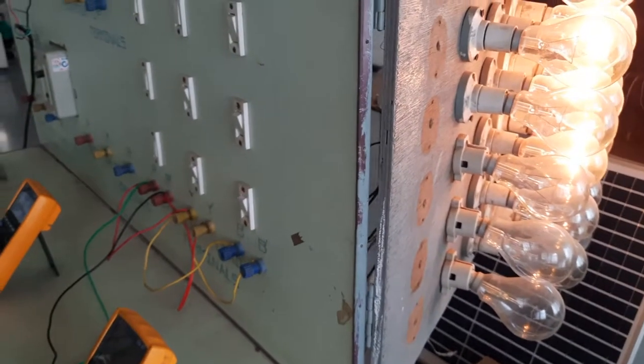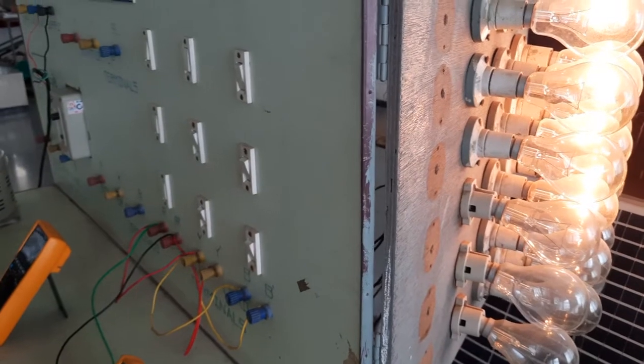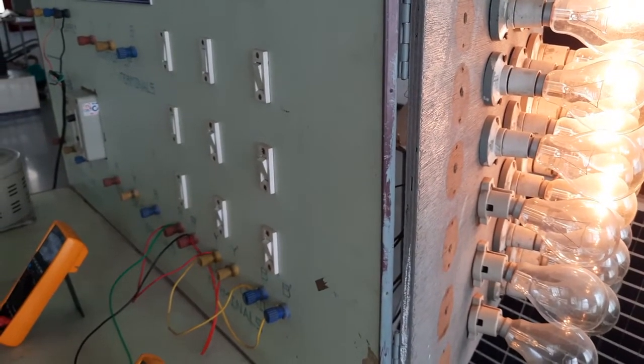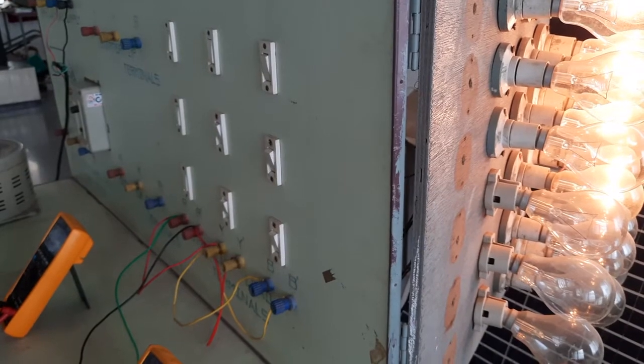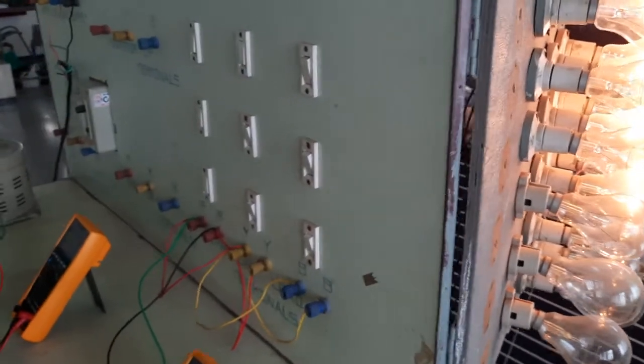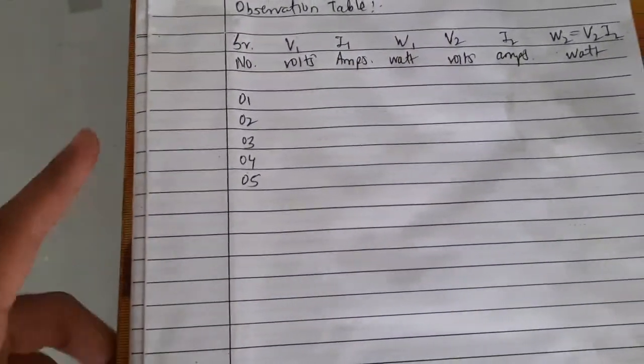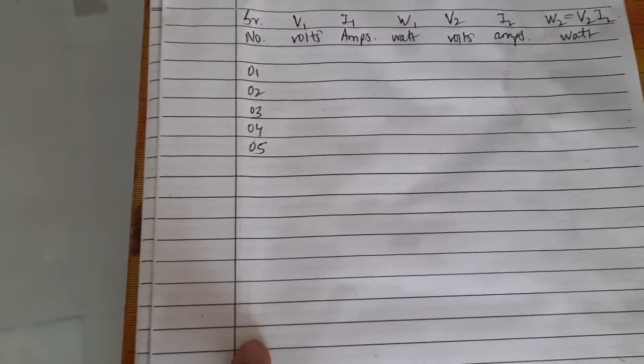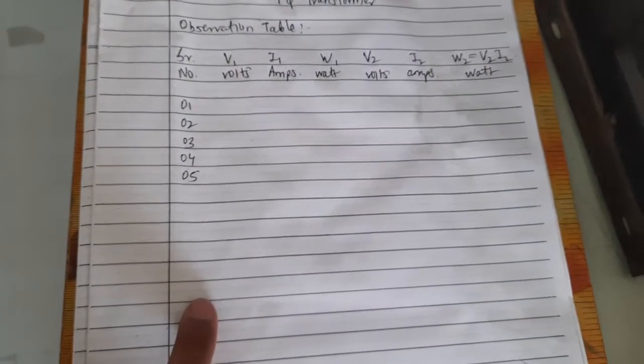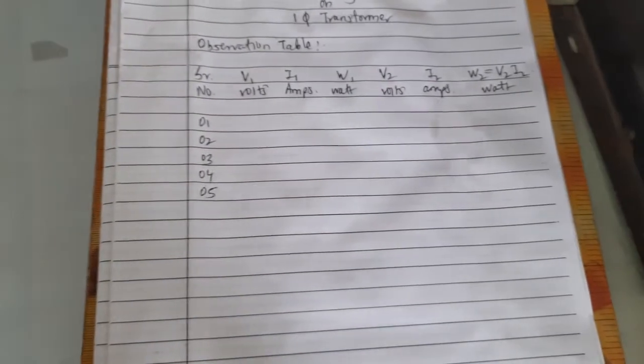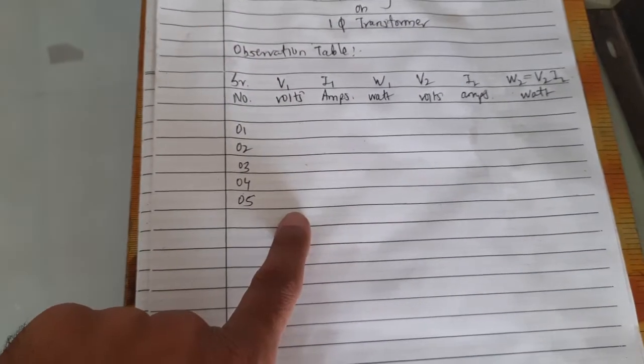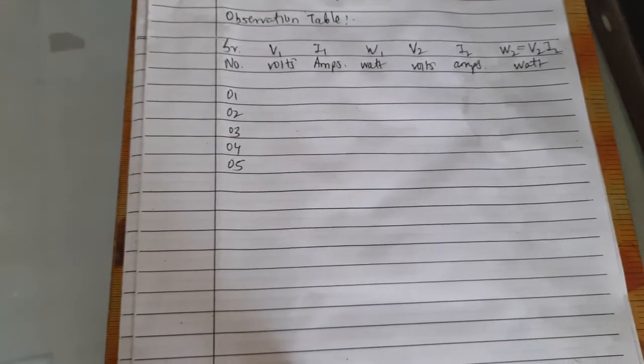So that is the direct loading test. We need to increase the load on the secondary side, and likewise take the readings of all the parameters from the primary side and from the secondary side. After taking all the readings, we need to find the output power W2, that is I2 into V2. Then we can calculate the efficiency, output upon input multiplied by 100, for each reading, and calculate regulation for each reading.